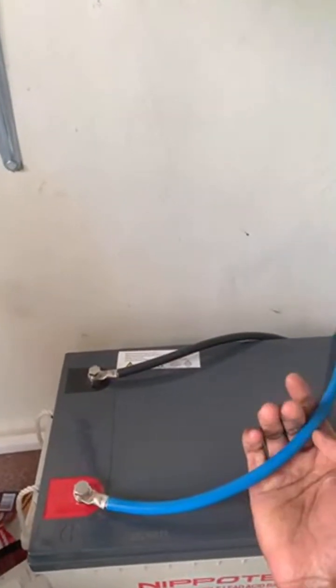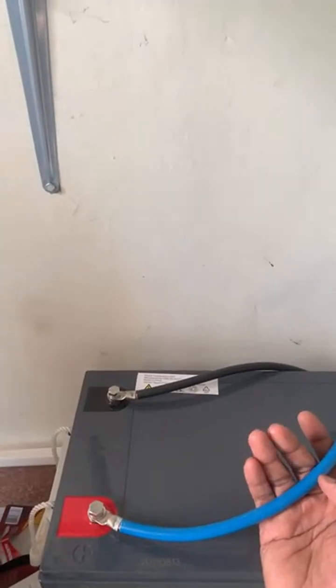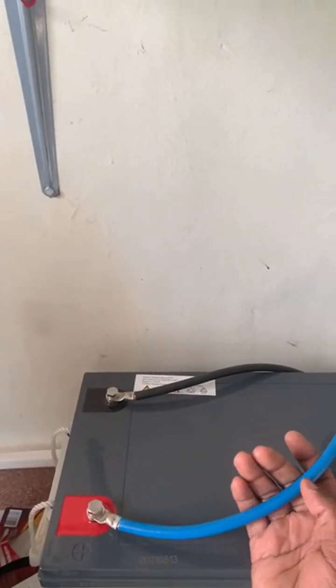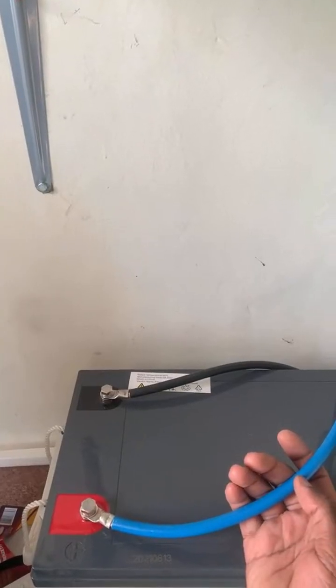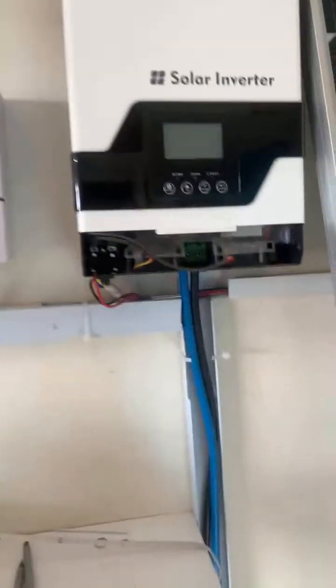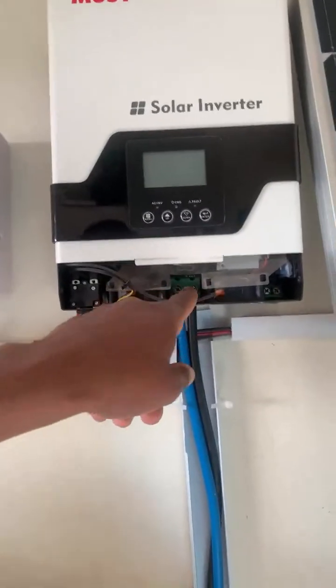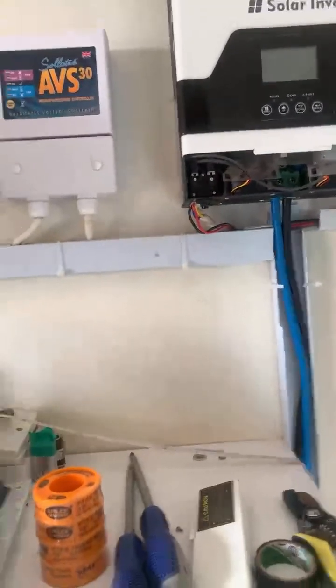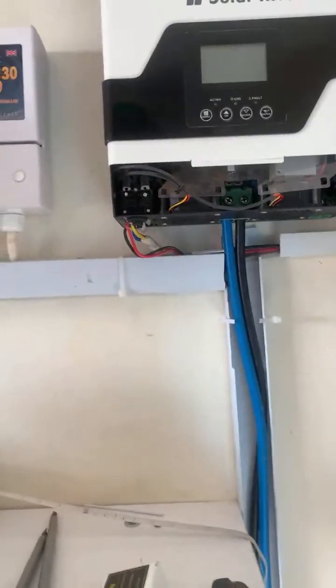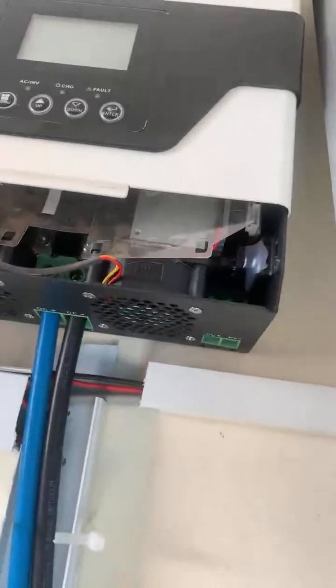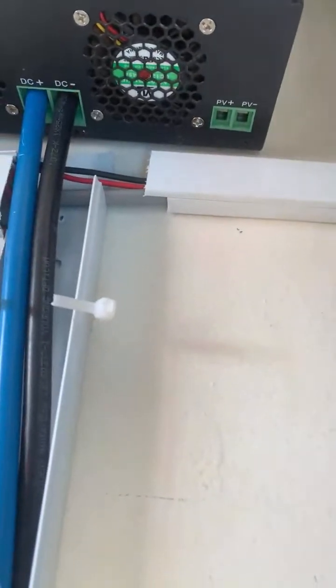So what we need to do in this scenario - you can see these are 25mm cables. There's something very special about these cables, right? At the inverter section, those cables are connected there for the battery. We normally have the connection for both the AC and the PV. So PV plus, PV minus, that's where the solar is incoming, and I'll be connecting that and showing it to you.